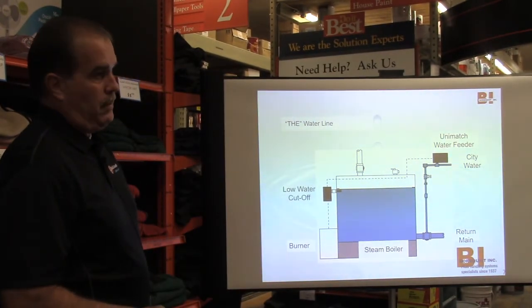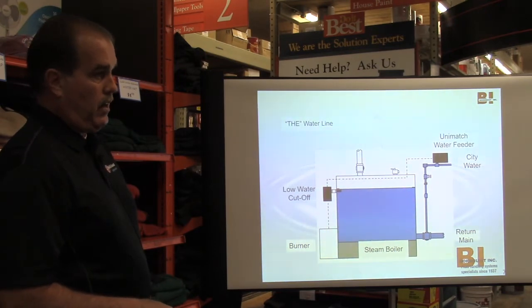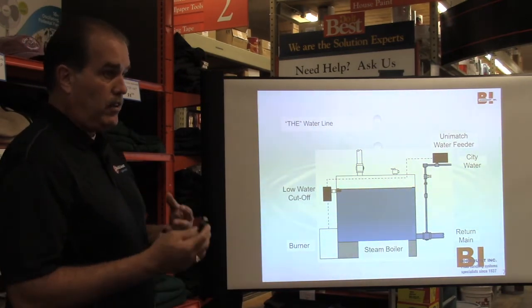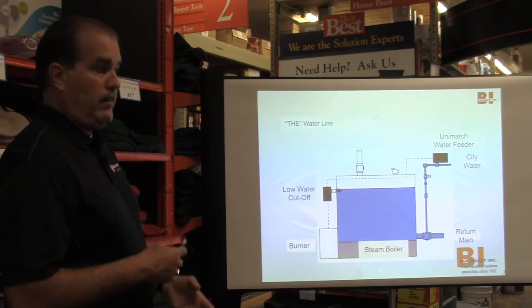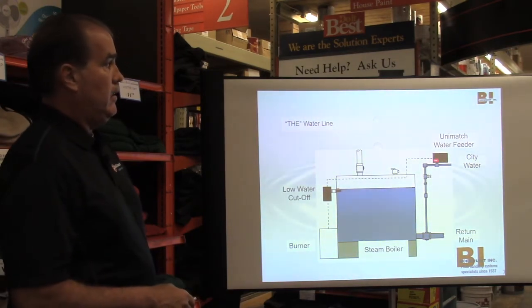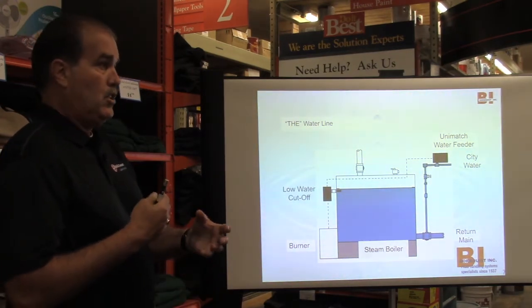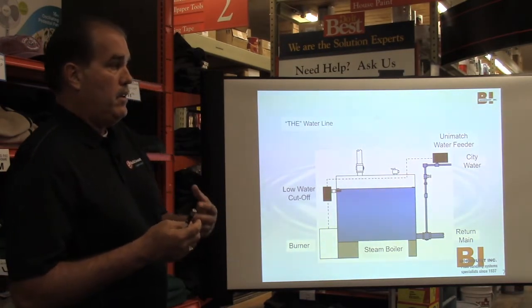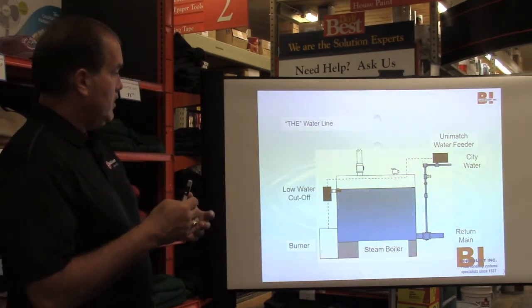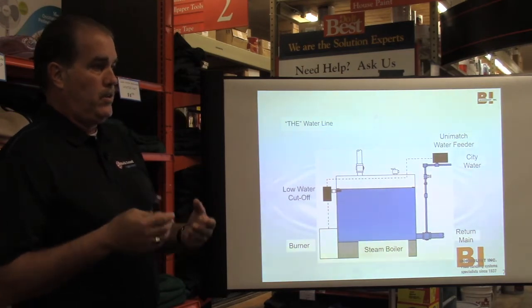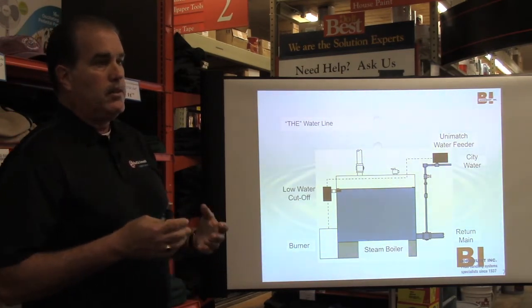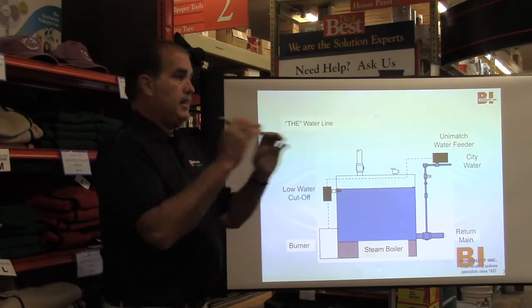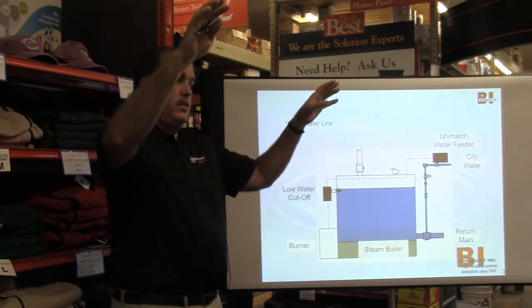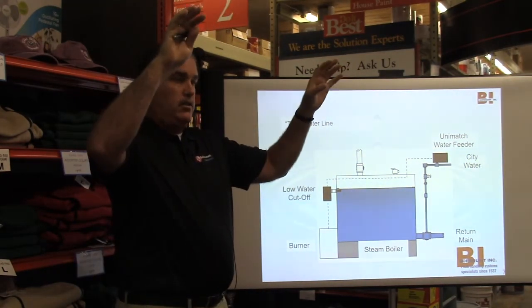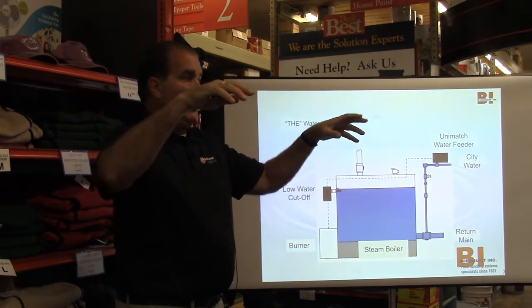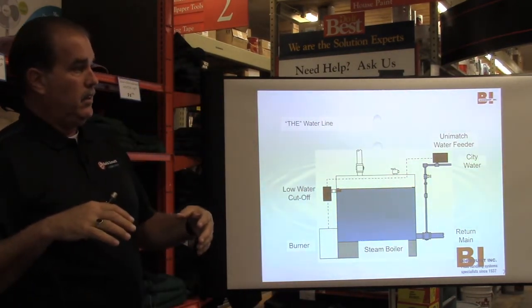Water feeders come in different flavors too. Some of them are electronic. Some of them are just like a solenoid valve type arrangement. They don't have any brains. Some of them, like the Unimatch water feeder, have adjustable time delays. And the reason they do that is steam systems are notorious for delay returns. A delay return means I'm making steam, I'm sending it out into the system, it's hitting my radiators, it's condensing back to water, and it's working its way back to the boiler.